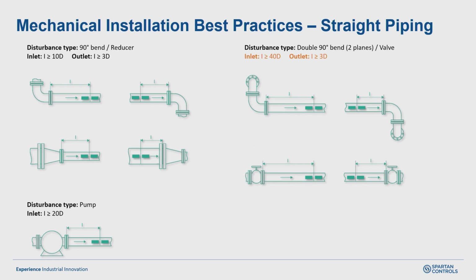So if we are talking about repeatability, if you just want a repeatable number, we can get that without meeting those straight pipe diameters. The exception to that, of course, is if you have a dynamic disturbance upstream like a control valve or a pump on a VFD. Those are obviously exceptions. But if you just have an elbow or an expansion or a contraction or whatever it is, then we can get 1% repeatability pretty much across the board.